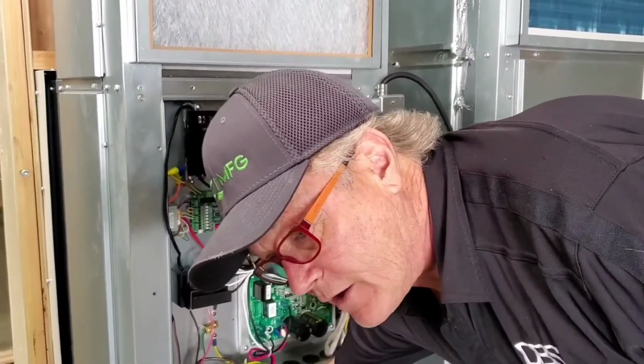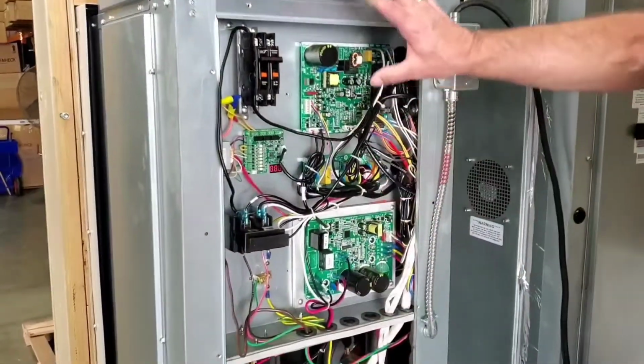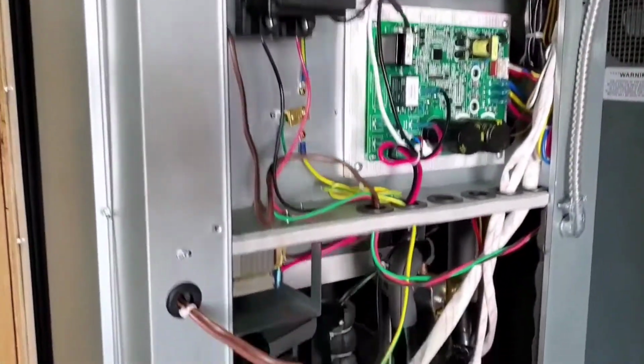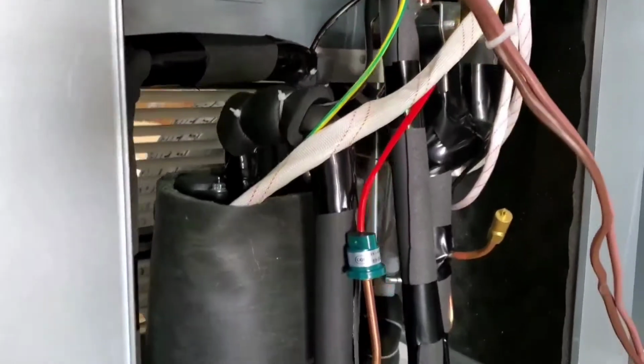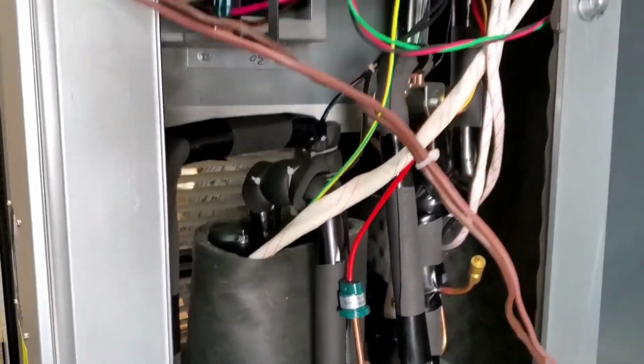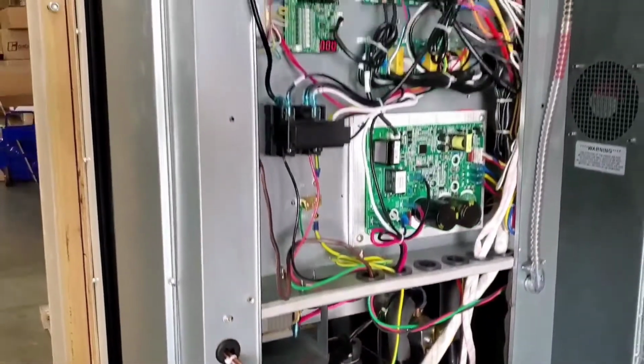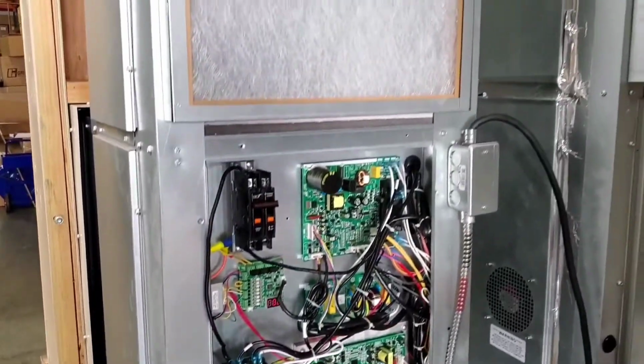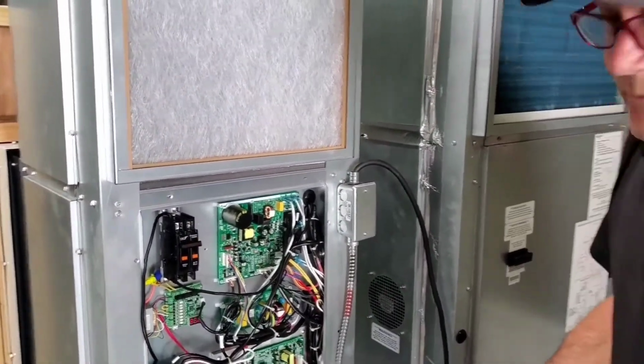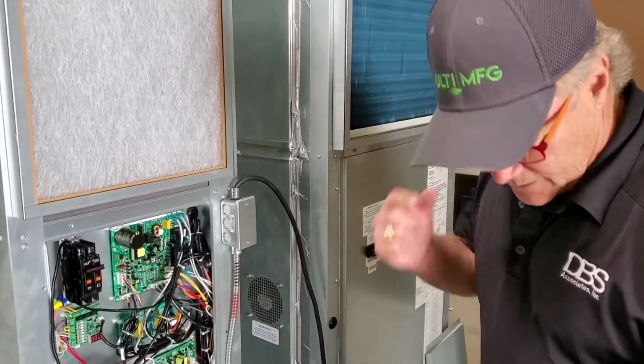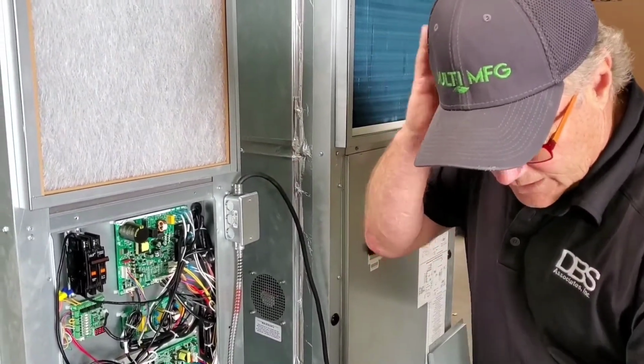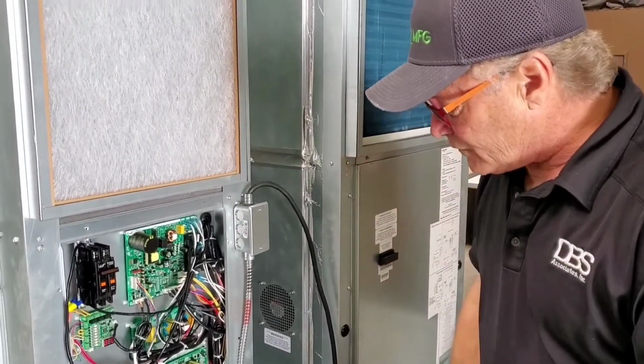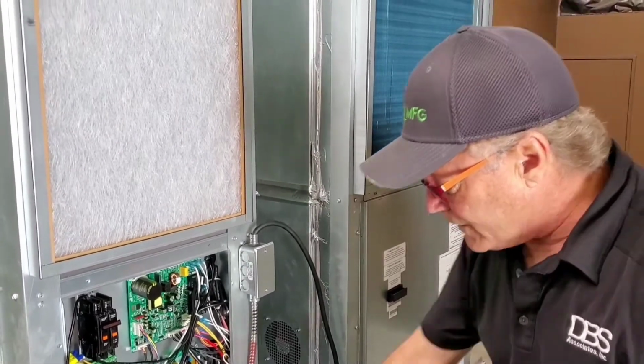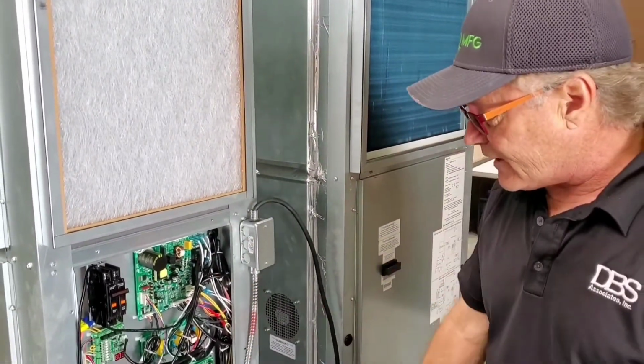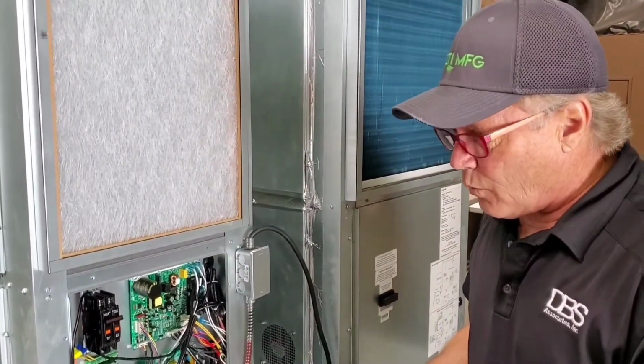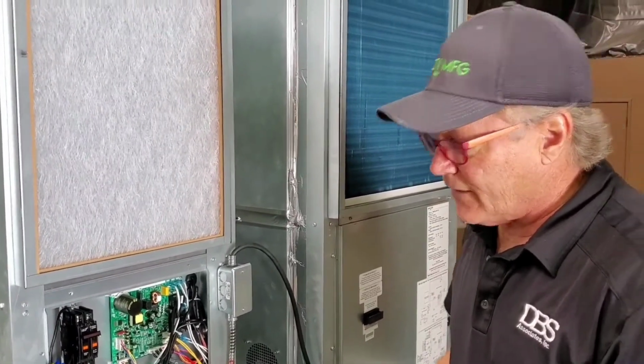The compressor is now energized and running. The heat strips are de-energized. I mean, not running. So right now it's going to start out, it's going to do a little test seeking through the sensors to find out how much it needs to ramp up to satisfy the heat load. Right now it's probably not going to ramp up too much because it's pretty warm out. We're running the heat at 87 degrees. It's 68 in the warehouse. So it's not going to be a real high rev. You will hear this going up and down as it satisfies the load. It'll seek what it needs to run at to be efficient.